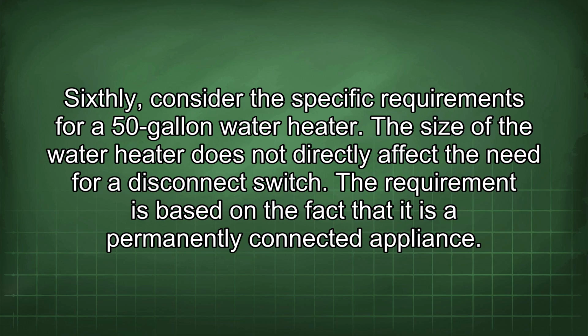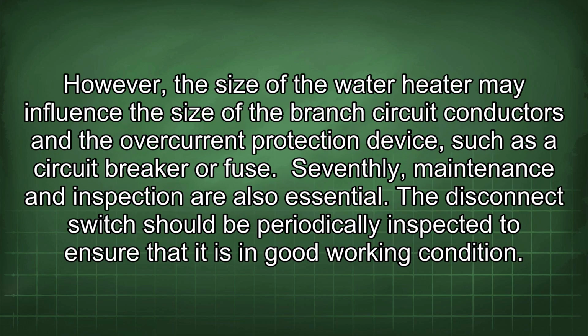Sixthly, consider the specific requirements for a 50-gallon water heater. The size of the water heater does not directly affect the need for a disconnect switch. The requirement is based on the fact that it is a permanently connected appliance. However, the size of the water heater may influence the size of the branch circuit conductors and the overcurrent protection device, such as a circuit breaker or fuse.